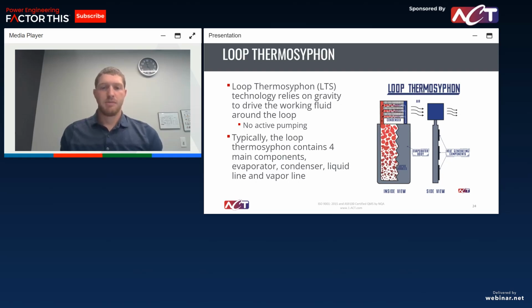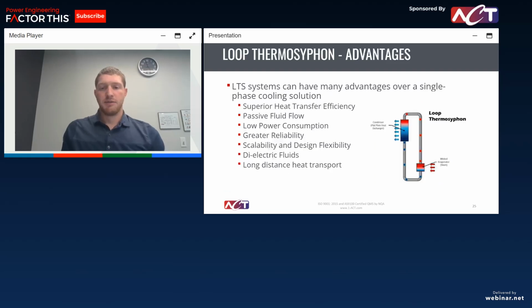So then the last two parts there, the liquid and the vapor line. In this example, it's shown here on the right. Our liquid and our vapor line are actually internal to the evaporator, which is a great advantage. You have that flexibility in other applications, especially if the components are situated far away from each other. You can have long, either flexible hosing or copper tubing, or whatever it needs to be. But as long as your condenser is above your evaporator, those liquid and vapor lines are pretty flexible.